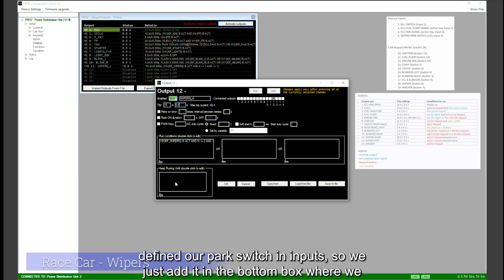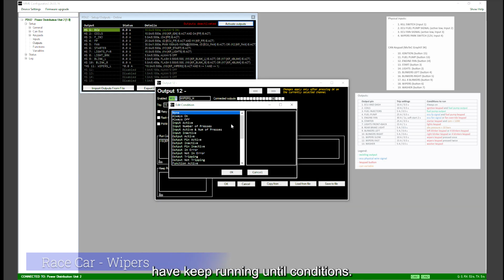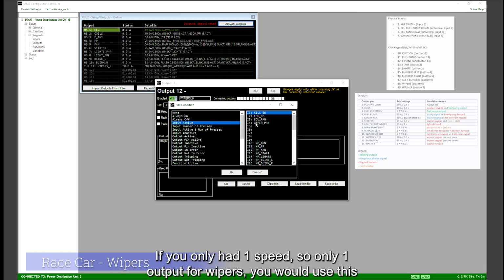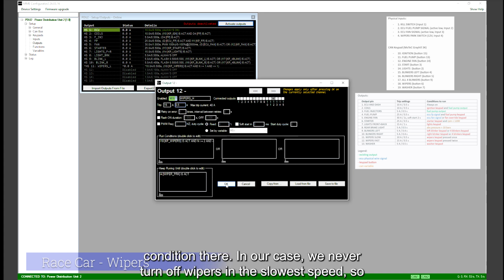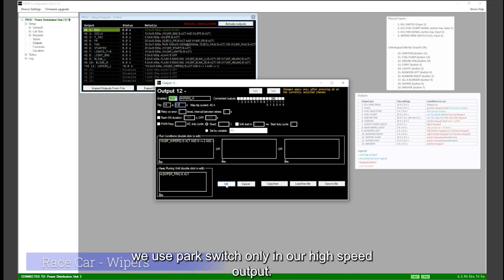We defined our park switch in inputs, so we just add it in the bottom box, where we have the keep running until conditions. If you only had 1 speed, so only 1 output for wipers, you would use this condition there. In our case, we never turn off the wipers in the slowest speed, so we use the park switch only in our high-speed output.